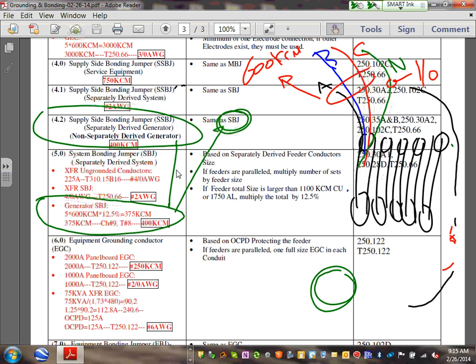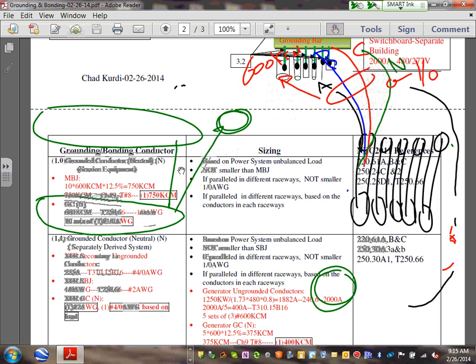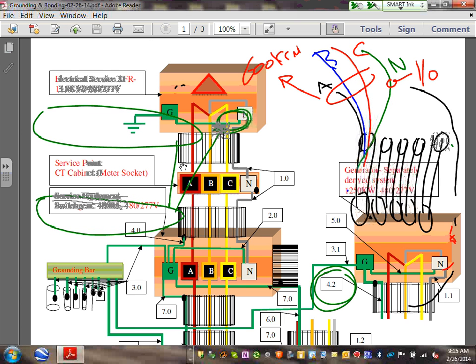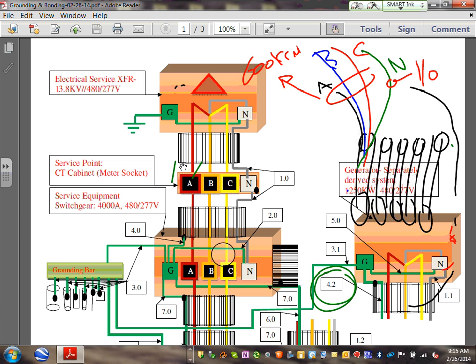Okay, last thing I want to size for this generator. I want to go erase that one. So the last thing I want to size, guys, for this mystery generator is at the generator, Derek, my friend, you have to take a grounding electrode conductor. Exactly like we did the service. You take a wire from the ground bar in the generator, and you take it all the way to that ground bar outside. Remember that one attached to the wall? You just attach it to it. Now, what size is that copper wire or aluminum? That 3.1, that's the last thing.